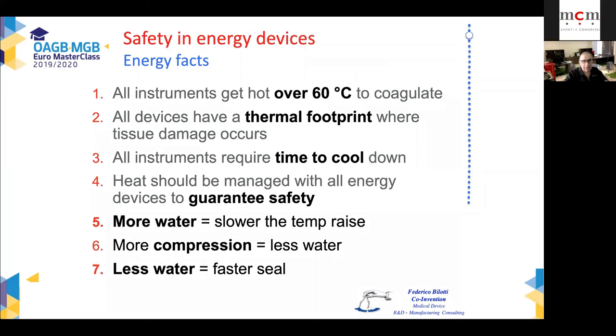Let's look at the important aspect of energy instruments. All instruments must reach temperatures over 60 degrees or they're unable to coagulate tissue. Thermal footprints are also left by all devices. The question is how large is this footprint, meaning how much damage the instrument causes laterally to the instrument jaws itself. All instruments require time to cool off. Important is to see how much time an instrument requires. The instruments on the market today should guarantee safety.